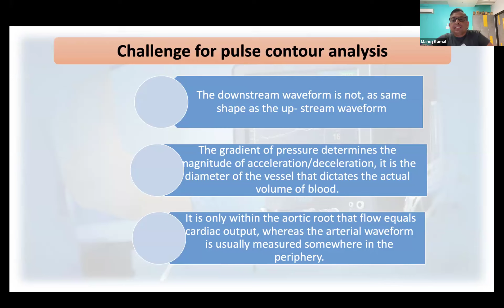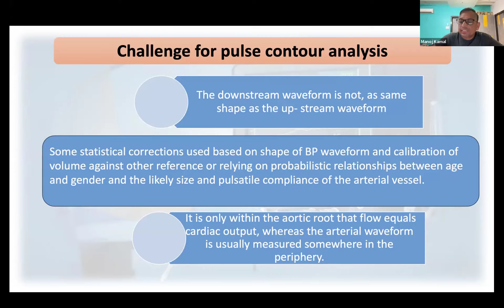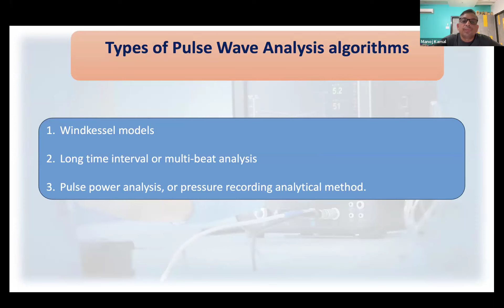So we use some statistical corrections based on the shape of the blood pressure waveform and calibrate volume against other reference, or rely on the probabilistic relationship between the age and gender, the likely size and pulsatile compliance of the arterial waveform to know the exact cardiac output. And pulse wave analysis algorithms use the Windkessel effect or long time interval or multi-beat analysis method or pulse power analysis or pressure recording analytic method.